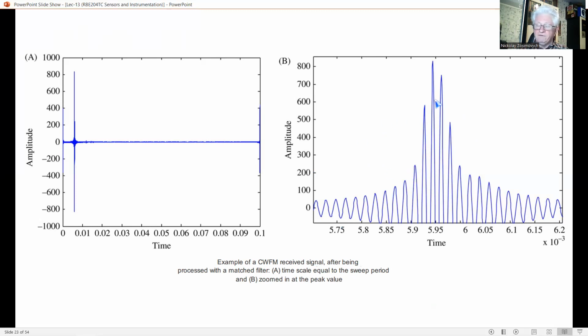Whether burst mode or continuous mode should be applied strongly depends on the requirement and the application. In general, the burst method is simple to realize, but is discontinuous and noise sensitive. This method is less sensitive to noise, but requires more complicated interfacing and certainly a signal processing tool. Generally speaking, this method outperforms the burst method in terms of range and noise immunity.